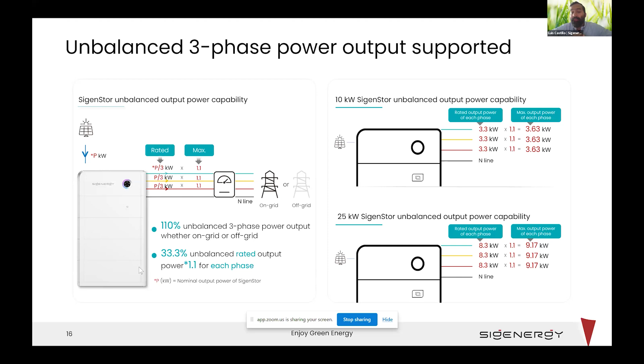For three-phase systems, we have the option to work with unbalanced loads, meaning a three-phase system where every phase feeds single phase loads that don't need to be balanced. The condition is that we offer one third of the maximum capacity of the inverter per phase. As long as you keep the maximum load per phase under that limit, you'll be able to work with unbalanced loads. This can happen during on-grid or off-grid scenarios, and you will still have the full capacity of your inverter.